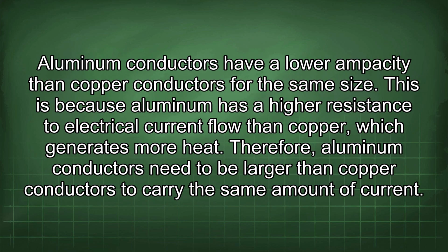Aluminum conductors have a lower ampacity than copper conductors for the same size. This is because aluminum has a higher resistance to electrical current flow than copper, which generates more heat. Therefore, aluminum conductors need to be larger than copper conductors to carry the same amount of current.